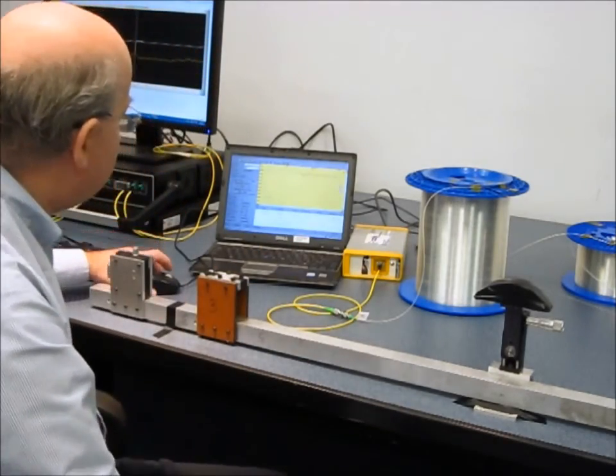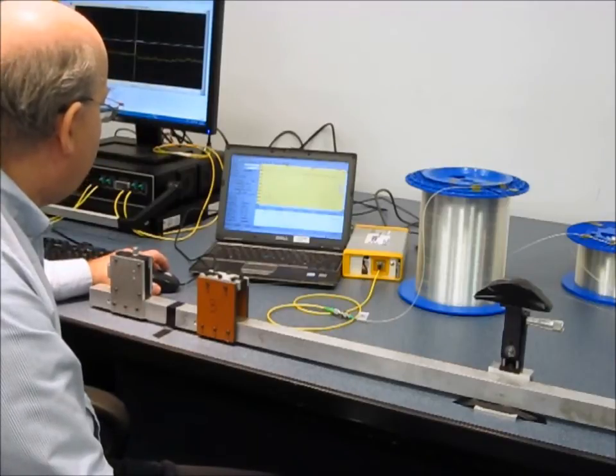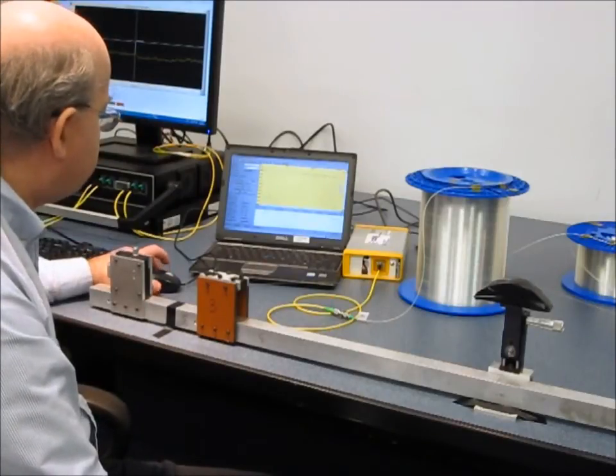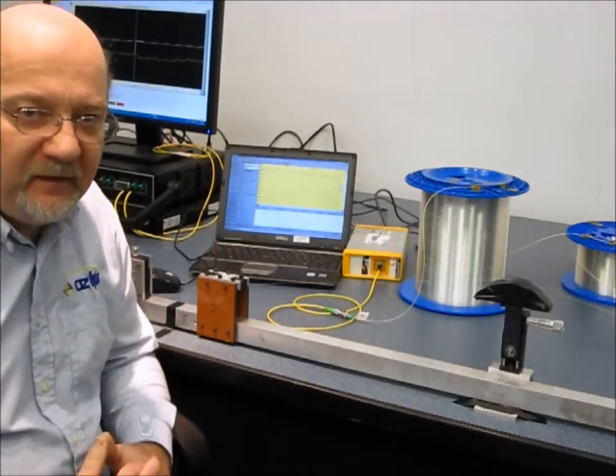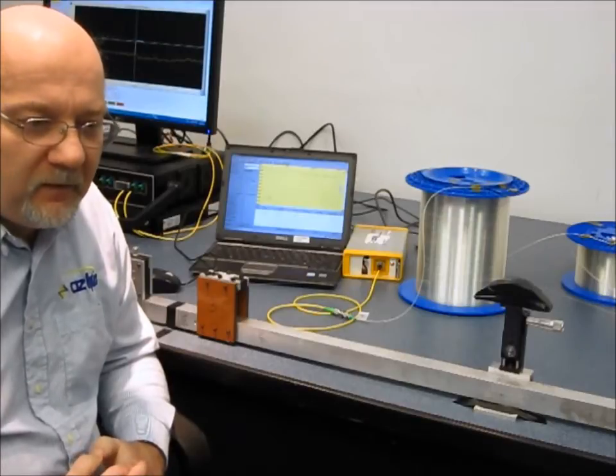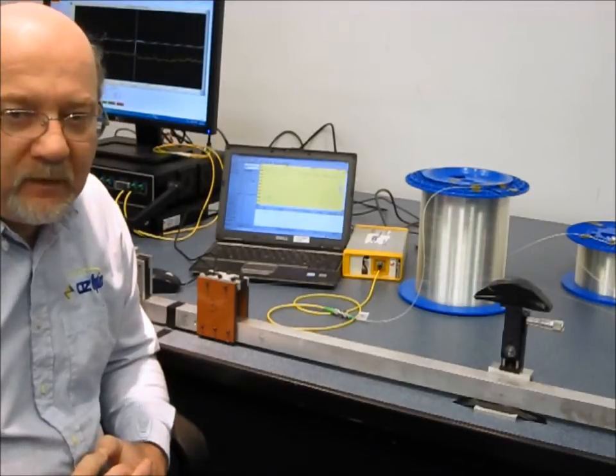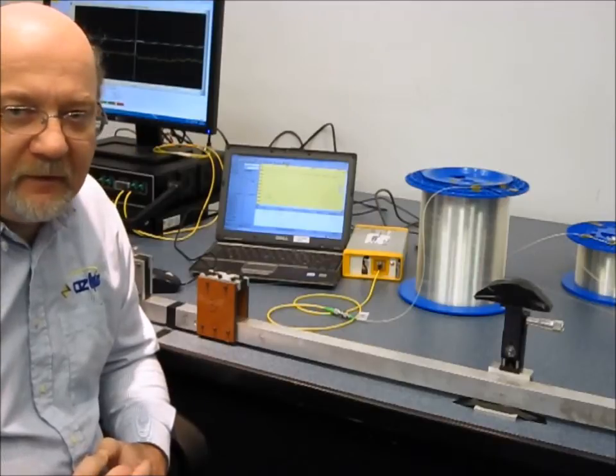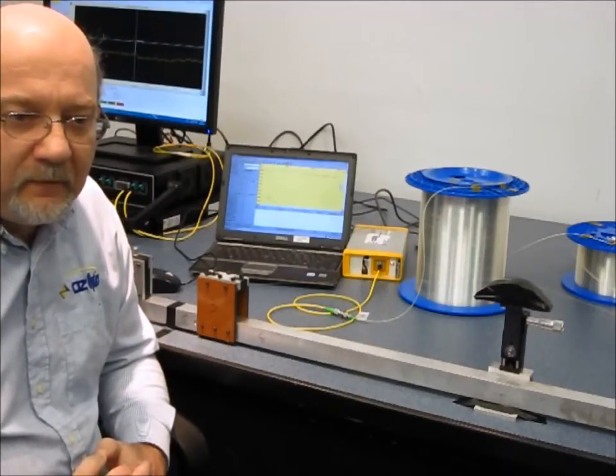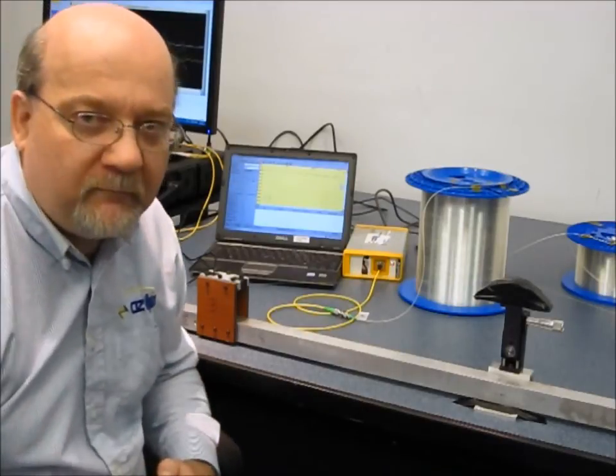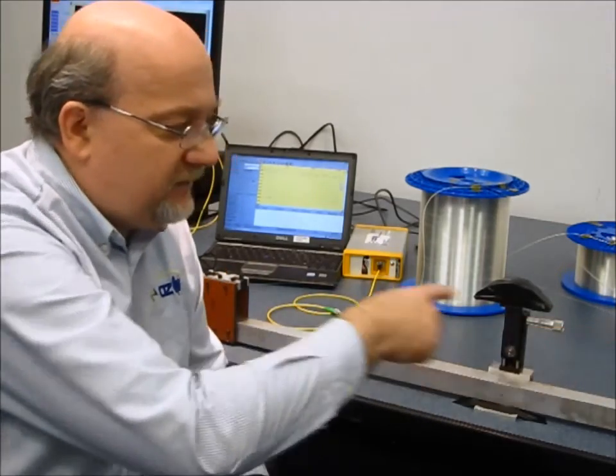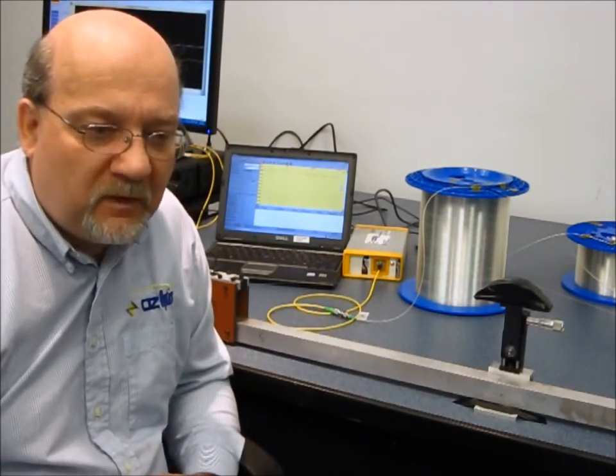So we're going to start a scan and see what we get. While it's scanning, let me tell you a few details about the settings we have used. We've set the OTDR to send out pulses that are 10 nanoseconds in duration. At this setting, it supposedly has a resolution of about 1 meter, corresponding roughly to the section over which we are stretching the fiber.